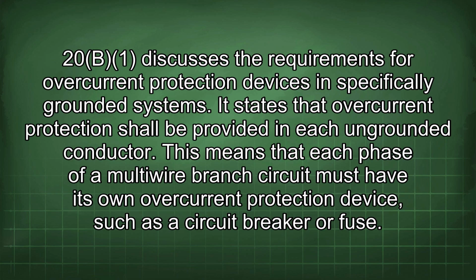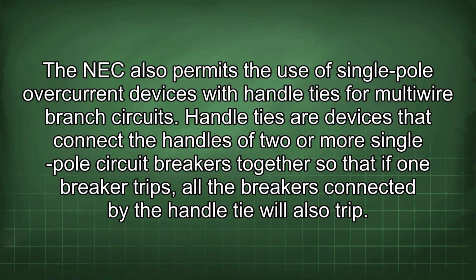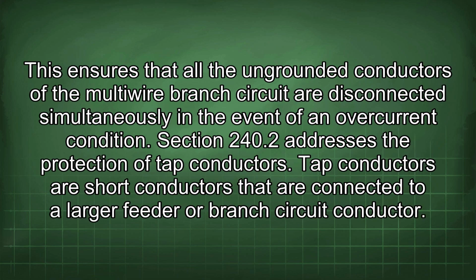The NEC also permits the use of single-pole overcurrent devices with handle ties for multi-wire branch circuits. Handle ties are devices that connect the handles of two or more single-pole circuit breakers together so that if one breaker trips, all the breakers connected by the handle tie will also trip. This ensures that all the ungrounded conductors of the multi-wire branch circuit are disconnected simultaneously in the event of an overcurrent condition.